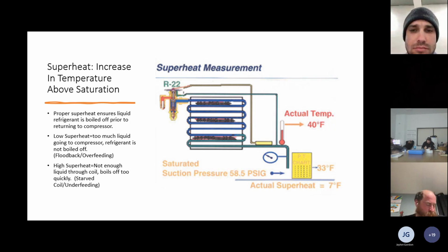Yep. That's what I was going to say next too. Your expansion valve is metering refrigerant, right? So it is adjusting. Too many guys go in, throw their temperature clamp or their FieldPiece on, get their pressure and see what it is in that moment. Oh, it's 20 degrees superheat, it's too high, I'm going to start opening the valve. Superheats are kind of like ice machines in that you have to be patient and give it time, because your valve is going to fluctuate.